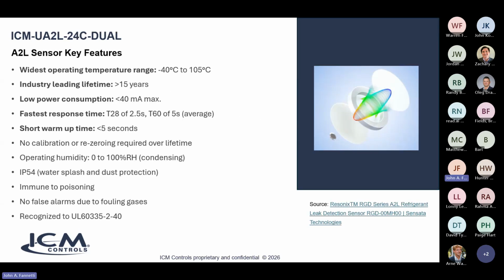So what's the key factor here? The key feature is the A2L sensor, and that's the little guy that does all the magic, okay? So the A2L sensor that's in here works off of sound, the speed of sound in an environment. It has a very wide operating temperature. It's an industry leading lifetime of better than 15 years, low power consumption. There's no calibration needed because it's not actually sensing the refrigerant itself, it's sensing the sound that is going through the air when the refrigerant is present and when it's not present. So it picks up the difference in that resonant frequency when the refrigerant enters an airspace. So no calibration needed means it's got a long lifetime.